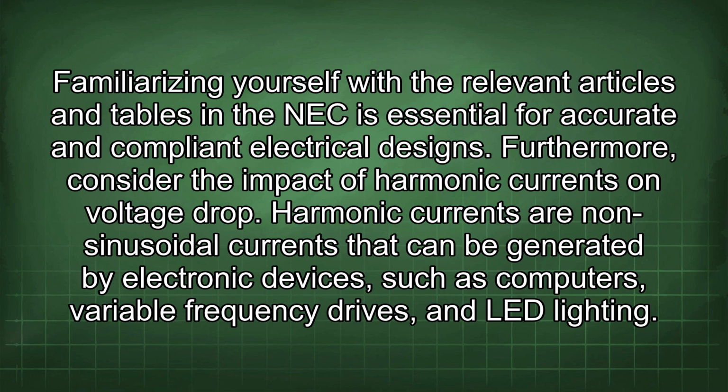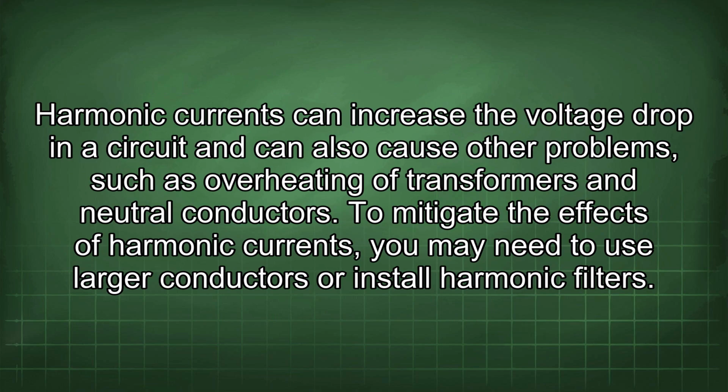Furthermore, consider the impact of harmonic currents on voltage drop. Harmonic currents are non-sinusoidal currents that can be generated by electronic devices such as computers, variable frequency drives, and LED lighting. Harmonic currents can increase the voltage drop in a circuit and can also cause other problems, such as overheating of transformers and neutral conductors. To mitigate the effects of harmonic currents, you may need to use larger conductors or install harmonic filters.